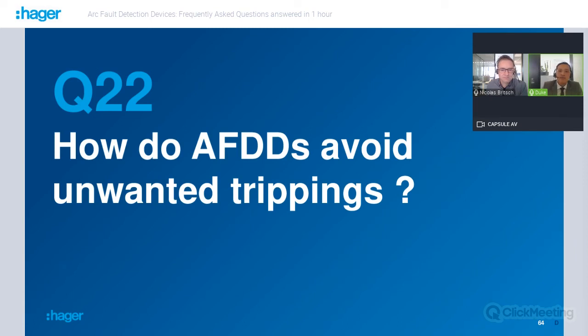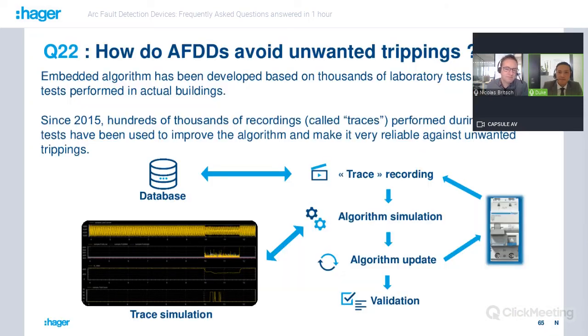So Nicolas, how do AFDDs avoid unwanted tripping? Actually, the embedded algorithm has been developed based on thousands of laboratory tests and field tests performed in actual buildings. Since 2015, hundreds of thousands of recordings that we call traces have been made during these tests and have been used to improve the algorithm and make it very reliable against unwanted tripping. So the process to develop the algorithm starts with trace recording. Then we use dedicated software to perform algorithm simulation, and then we can improve the algorithm, update it, and finally go to the validation steps, and then we can release the product in the market.